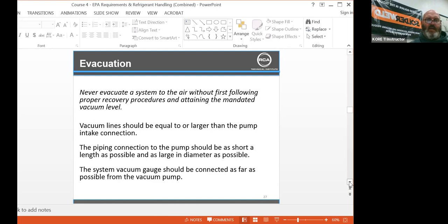Evacuation, the piping connection to the pump should be as short in length as possible and as large in diameter as possible. The system vacuum gauge should be connected as far as possible from the vacuum pump. How many times have you guys seen the micron gauge right up against the pump or on the pump?